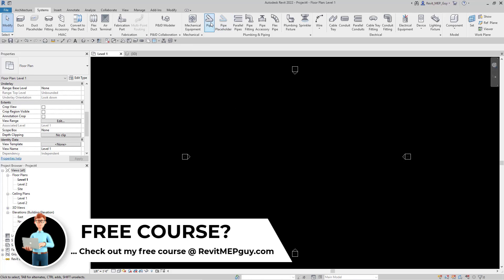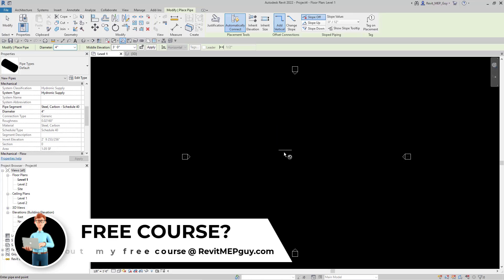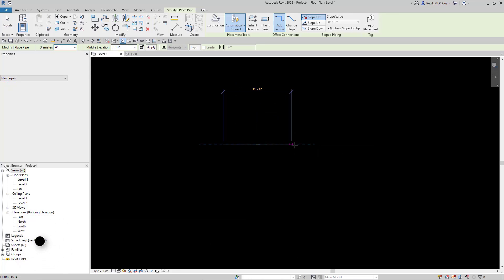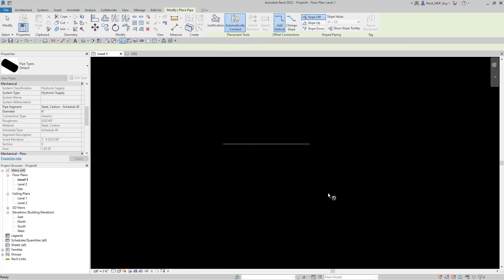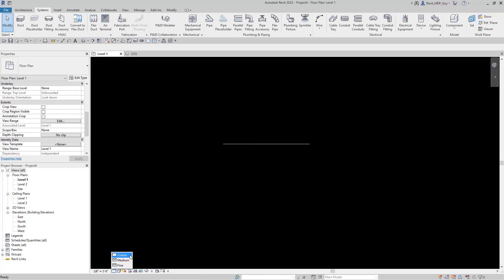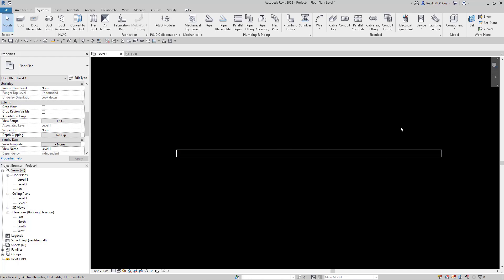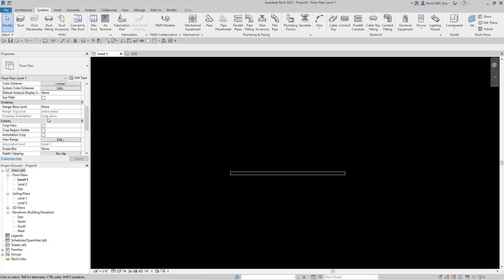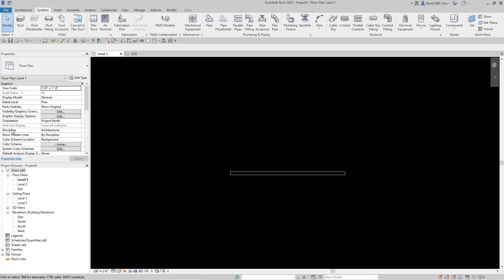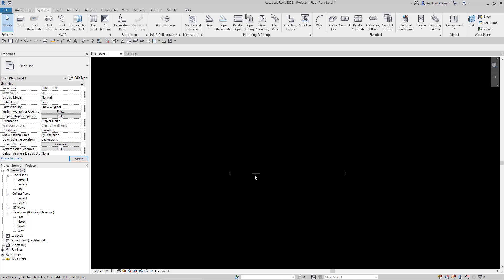So what happens if we draw a pipe that's below four feet, let's say three feet? As you can see, my pipe is now showing up. If I change my detail level to Fine, you'll see that the pipe shows up as a two-line pipe. We want to be able to draw pipe at any elevation we want, so we do not want to use an architectural view or discipline when drawing our pipe. We want to switch this to a Plumbing or Mechanical view, and that way our pipe will always show up no matter what elevation we draw it.